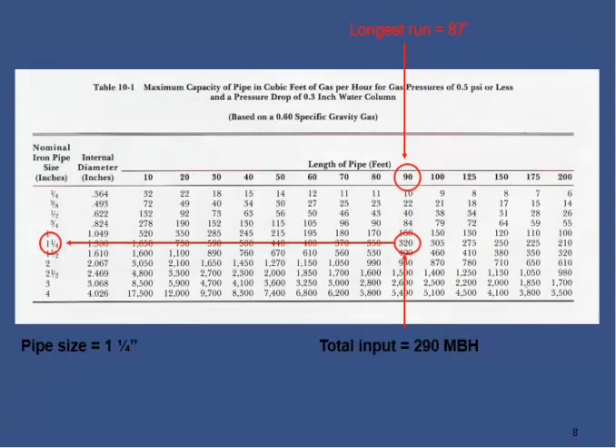To start with the sizing, we refer to this column giving the length of the pipes with intervals of roughly 10 feet. Ours being 87, which falls between 80 and 90, and our demand is about 290 MBH. Between here and here, when we refer to this, this will become the pipe diameter. The starting point from the gas meter outlet, our pipe size will be 1¼ inch.